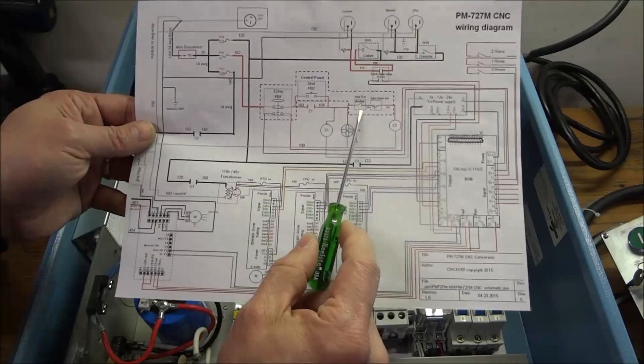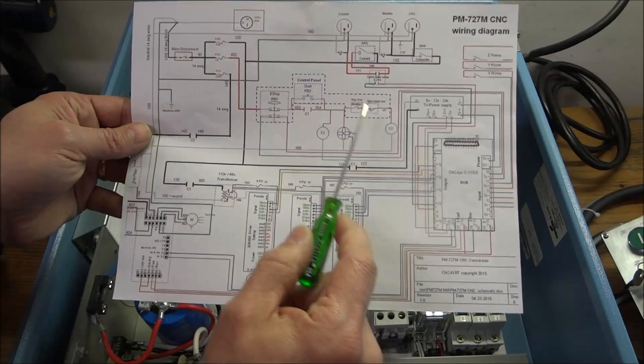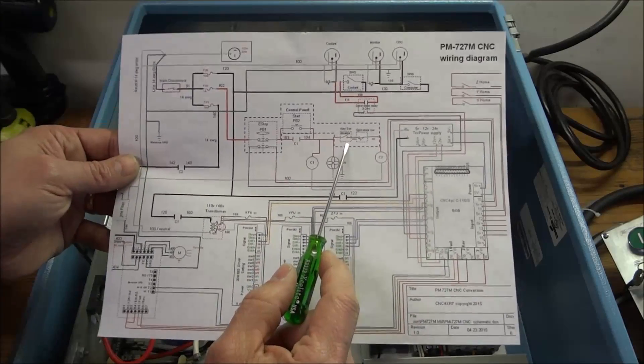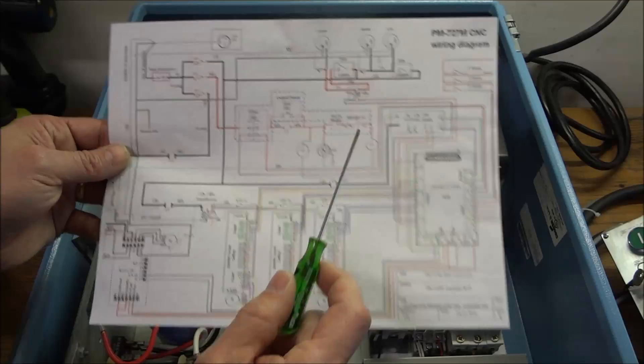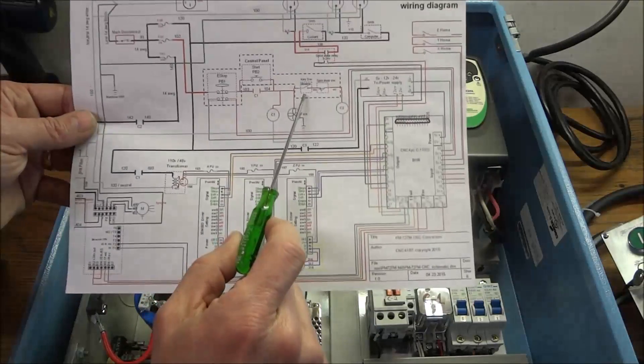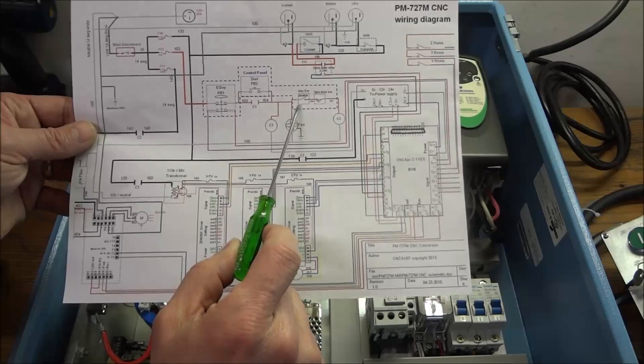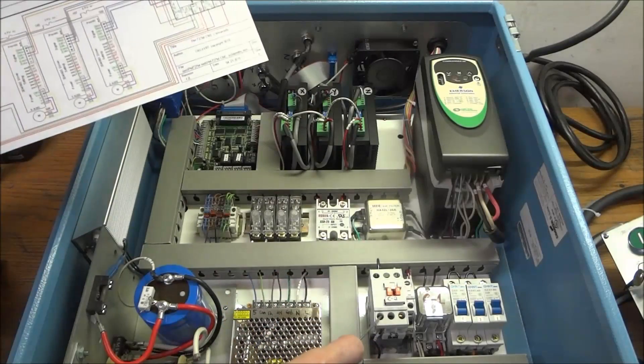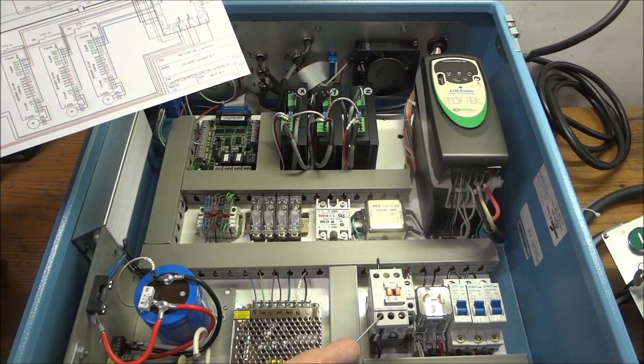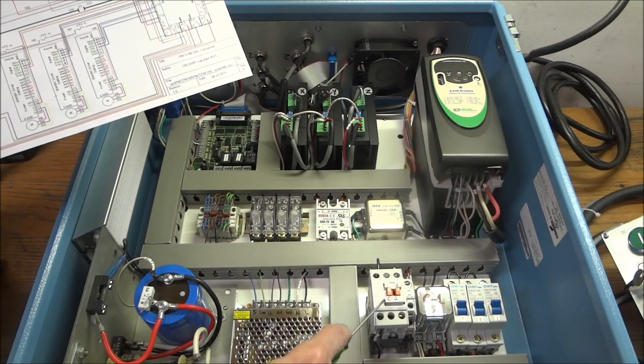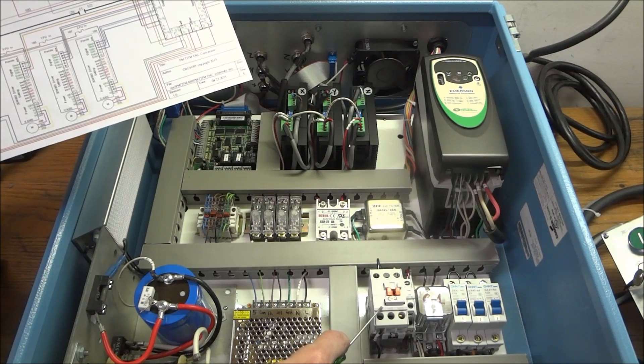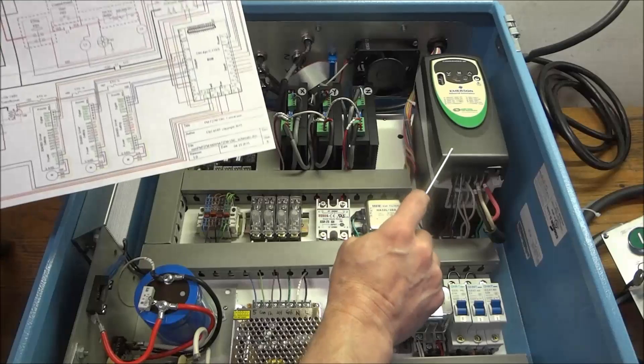Now likewise, the key switch for the C2 contactor, the reason I put this key switch in here is to disable the VFD. If you turn this key switch and open up these contacts, then C2 contactor will de-energize and the contacts will pull open and this will shut down the VFD.